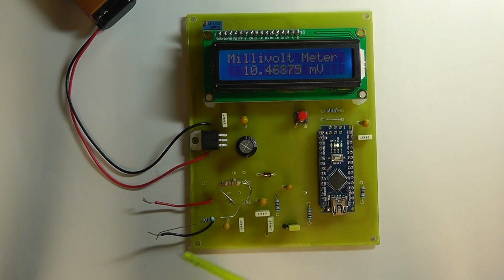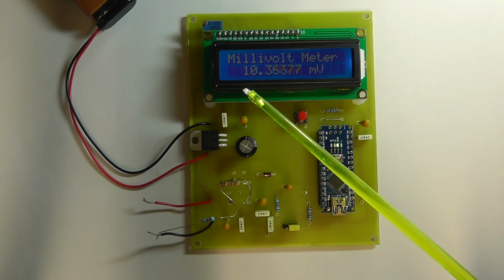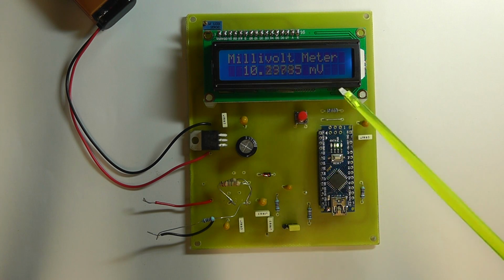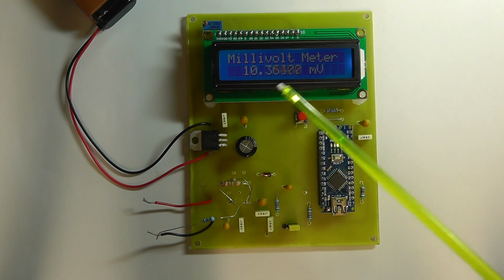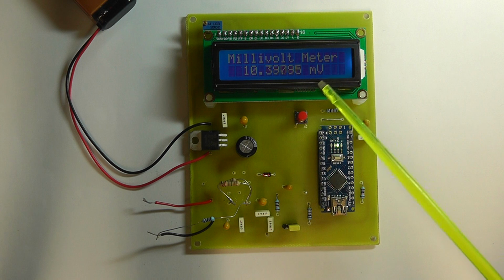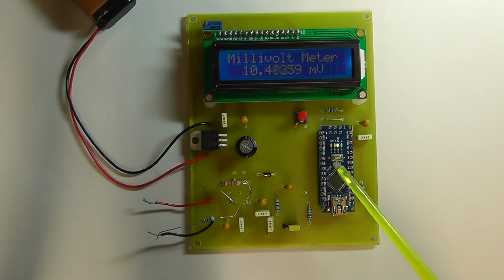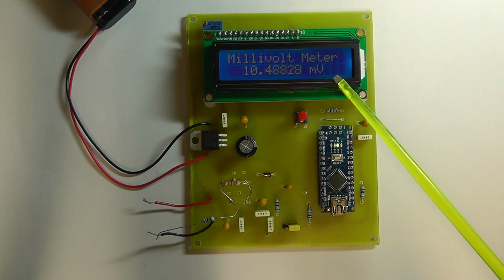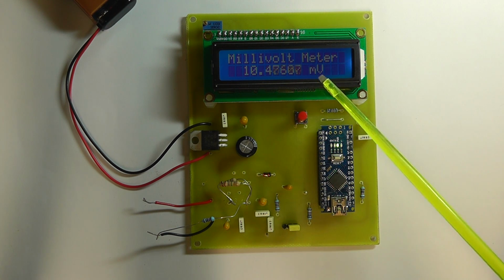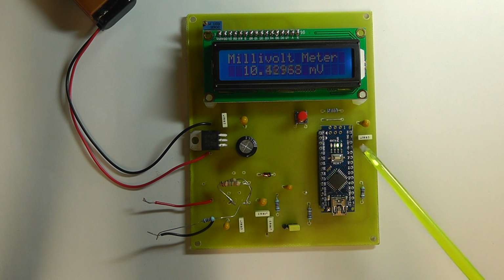At the moment I've got nothing connected here, but the meter is giving a noise reading of about 10.3 millivolts. You can see the millivolt indication on the display. In the software, if the voltage is below 1 volt I show the millivolt reading, and if it's above 1 volt I show the voltage reading. That's all handled within the software.